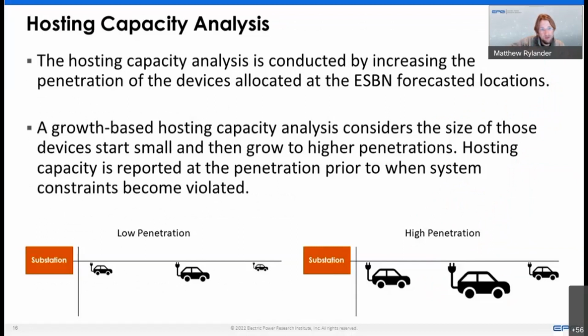Before I get into the growth aspect, I want to highlight more on the hosting capacity analysis. The terminology might be vague, but there are different ways to do hosting capacity. The way we're utilizing it here is not from a generation aspect - we're looking at hosting capacity by how much load can be accommodated. Most common uses ask how much more generation before a problem occurs, but here we ask how much more load growth we can have before a problem occurs, and it's not focused on single point connection locations.